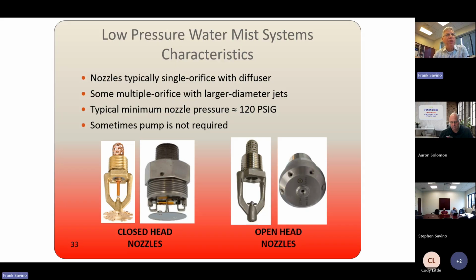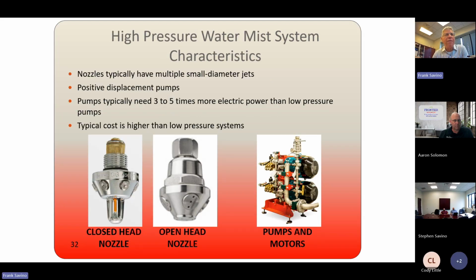So the requirement on every single nozzle to get approval is to have that filter, but then there's also requirements upstream of that at the valve, at the water source. You need to be filtering the water and screening out particulate matter there. And when you think back at that high pressure, how it had tiny orifices. Okay, this is an open nozzle that you see here. These are actually more susceptible to getting clogged. So in the design process, I can't overemphasize enough the importance of making sure that your water quality is clean and filtered.